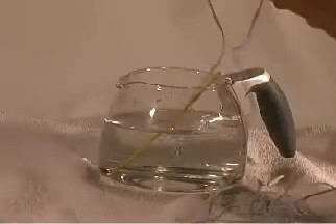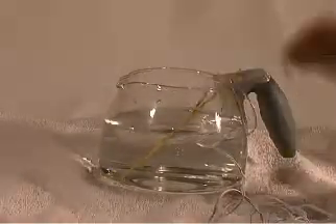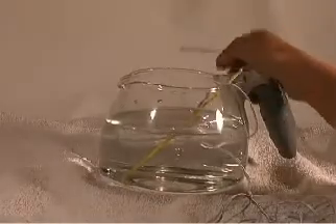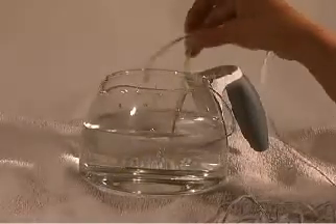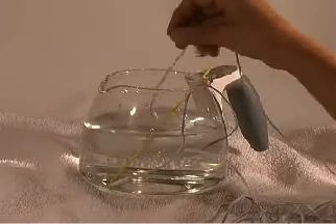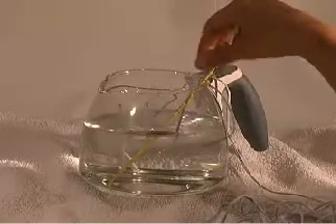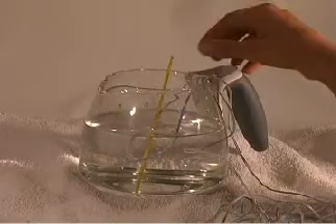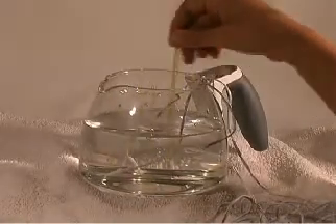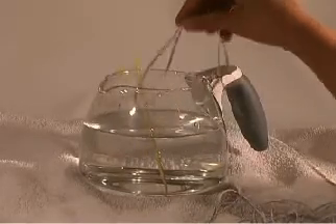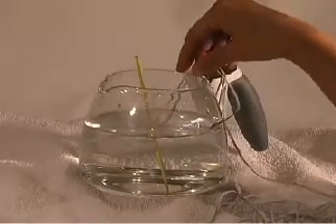Well, what I noticed is the top of my platform is heightened a little bit, and somebody put a heating pad underneath my ice water bath. So when I had one of these probes down low, it wasn't measuring the same temperature of the water, which is supposed to be homogeneous by stirring, as the one at the top. And if I had been more careful and followed my SOP, I would have stirred slowly during. I would have looked at the tips of the probes to make sure that they were near one another.